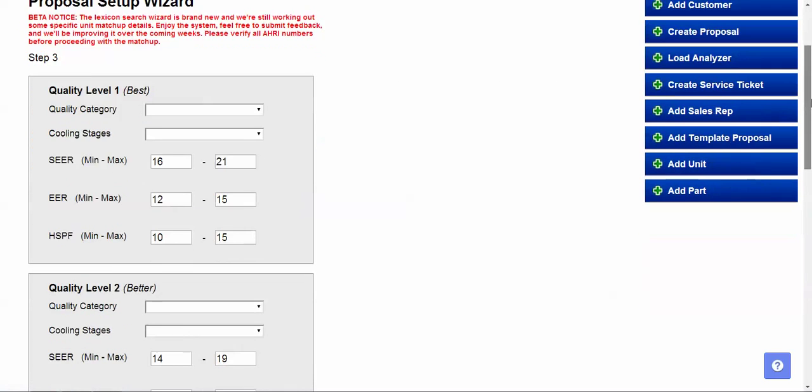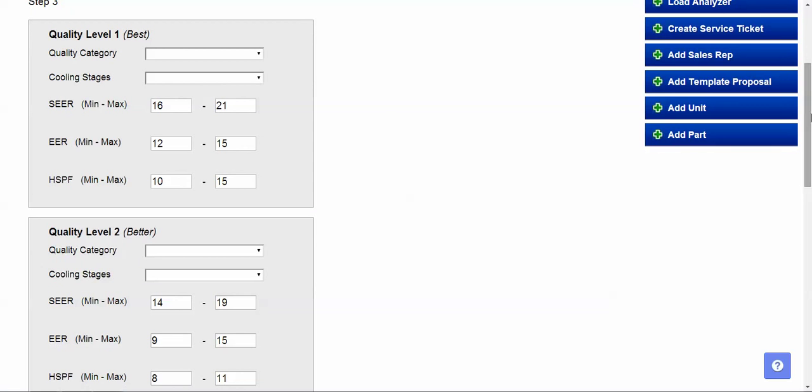So while my minimum is 25,000 BTUs of cooling on this house, I want to show an inverter. And so I'm going to have to show an inverter on my best model, I'm going to have to go above the size of the next size up, above the half size. So they don't make a 2.5 ton inverter, so I increased my maximum cooling up to 36,000 so that I could bring up my cooling capacity on that size so I can see it.